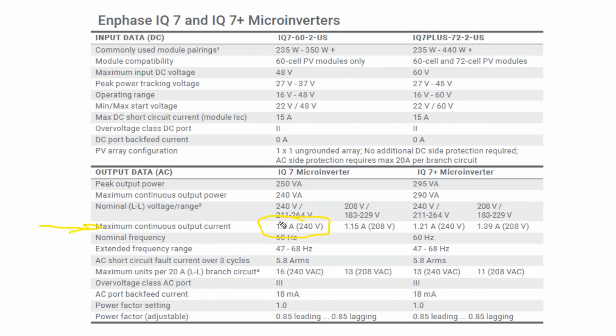The microinverters are outputting 1 amp each, and Enphase forces their system onto 20 amp breakers. And electricians know that you can't just put 20 amps of output capacity on a 20 amp breaker, because then the breaker will trip. You have to do less than that. And for NEC, the standard AC oversize is 25%. And so on a 20 amp circuit, you can only have about 16 amps of output capacity. And what that means is on the Enphase microinverter that outputs 1 amp, you can only have 16 microinverters per 20 amp branch circuit. And so this is pretty easy.